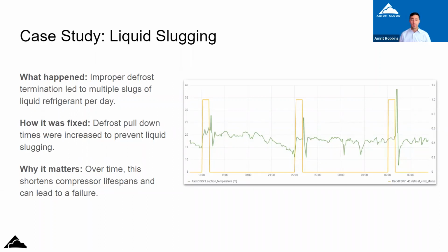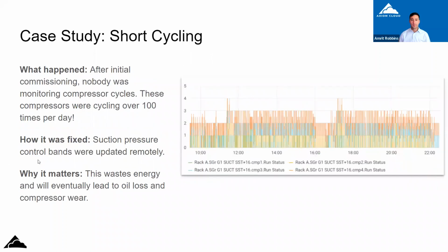And so this is the kind of thing that won't cause a compressor to explode on day one, but it will slowly wear down the compressor over a period of weeks or months, and take a 15-year lifespan and shorten it to 5 years or something like that. So this is an example where the fix was very, very easy, basically lengthening the pull down after defrost to ensure a smoother transition back into normal operation and eliminate that liquid slug entirely. Let's keep on going to the next one here.